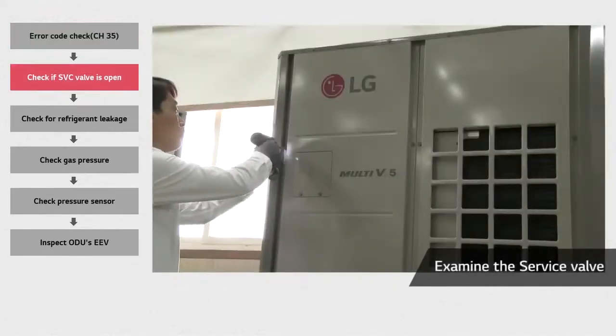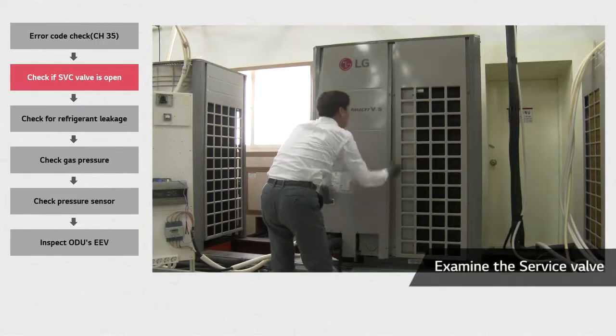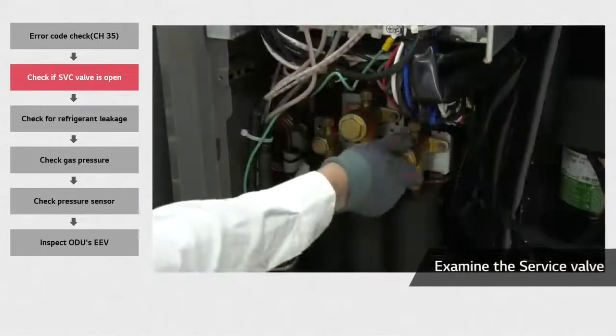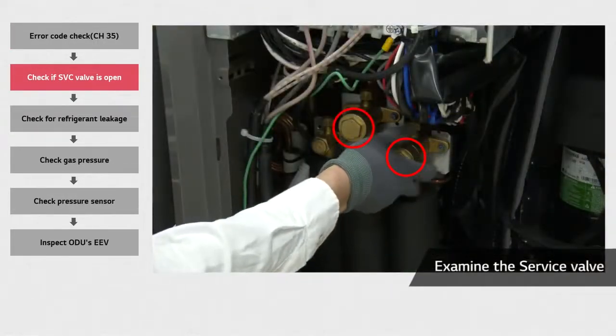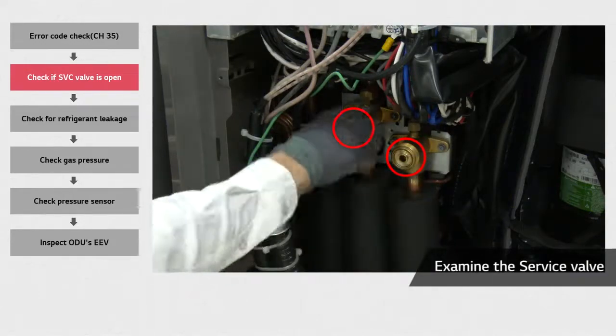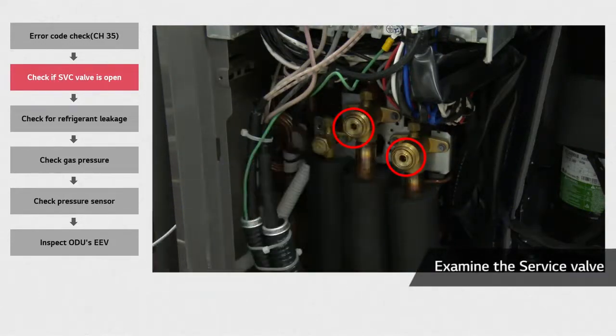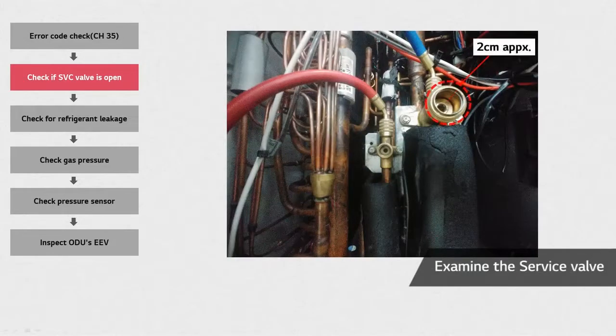To solve this error, start by removing the front panel of the outdoor unit. Remove the service valve cap to check if the valve is open or closed. It should be open. You can tell whether the valve is closed or open depending on the position of the top ring relative to the pipe. If the ring is about 2 centimeters inside the pipe, you can assume it to be closed. If it is almost parallel with the surface, the valve will be open.